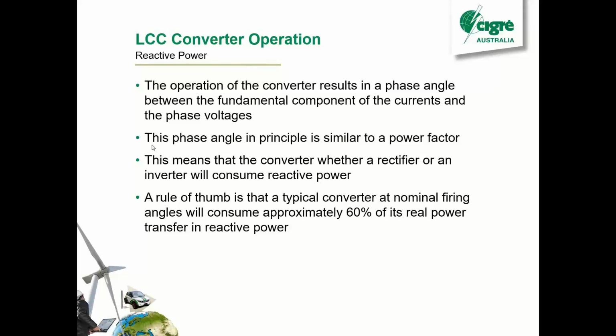So the rule of thumb is it's about 60%. So if you're sending 1,000 megawatts with your DC link, that means you're going to have to supply 600 megavars of reactive power at each end, which is a real Achilles heel of the LCC, because that's a lot of capacitor banks to do that. So you need a lot of area in the substation to have that, and lots of filters, lots of circuit breakers, lots of switching. All of those things cause issues, wear and costs. So it's one of the real key disadvantages of the LCC.